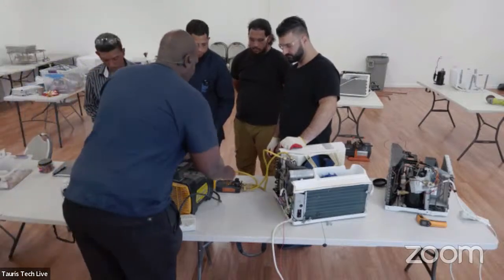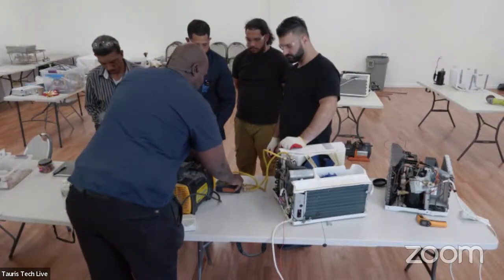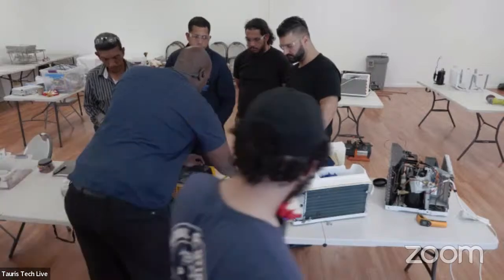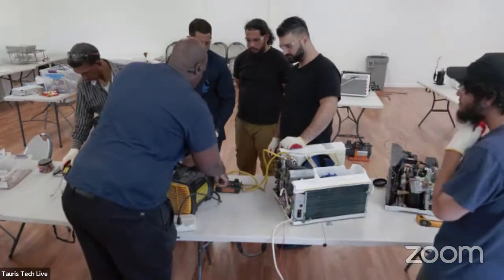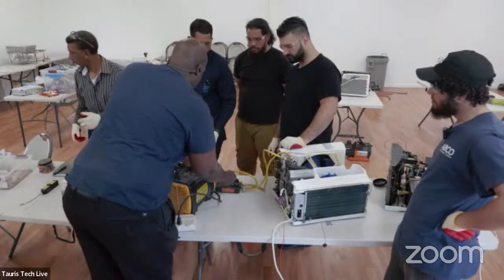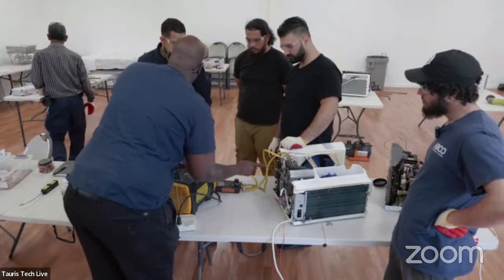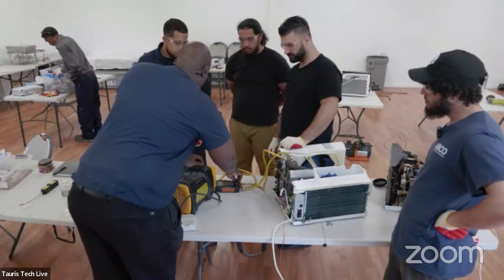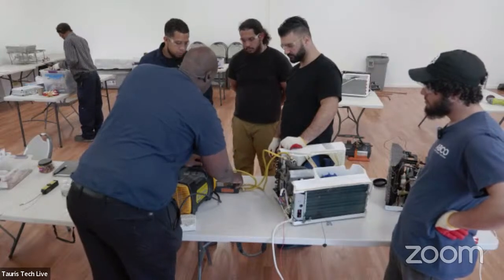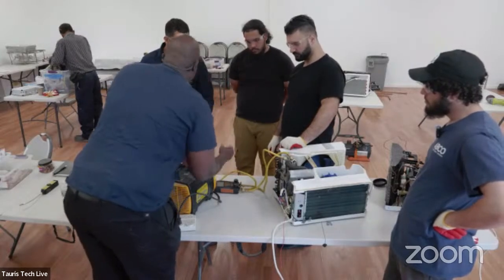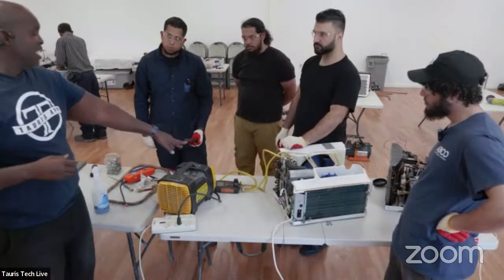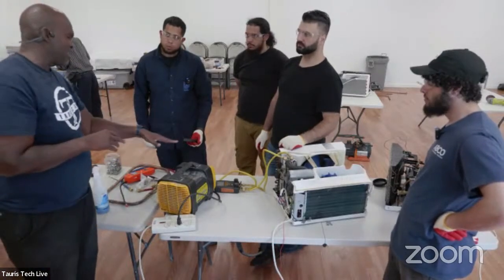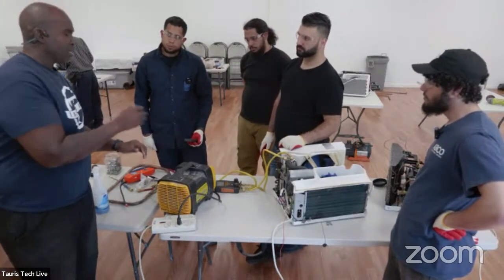If I close these valves, the pressure is going to go back up. It's still refrigerant — pressure just went right back up. That's why you got to keep going, keep checking, make sure you get all that refrigerant out. Because if I disconnect, even if I say okay, I'm at 0 inside, good — oil, feel it, it's a little slow.